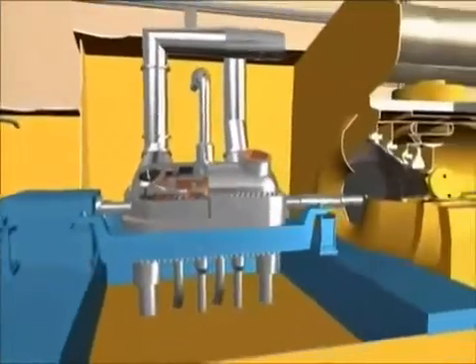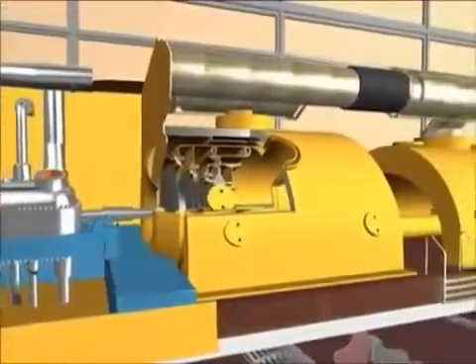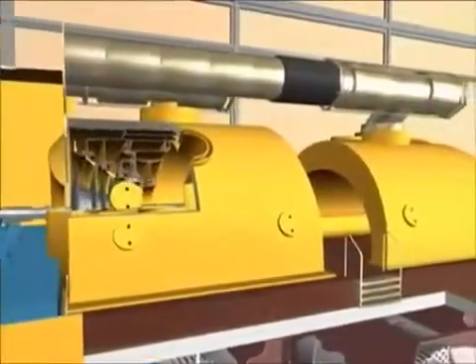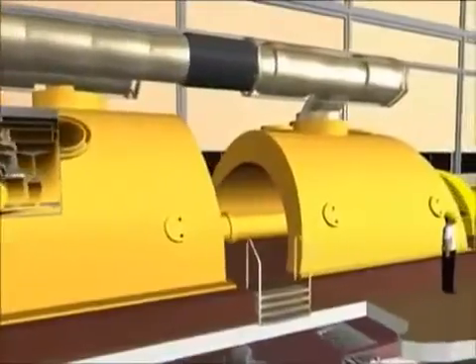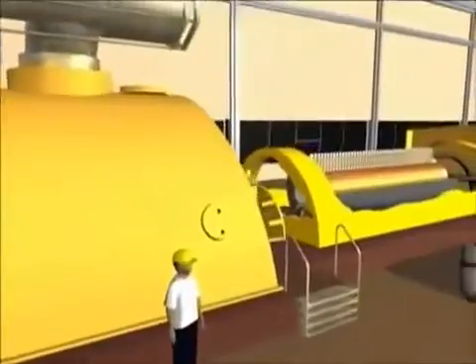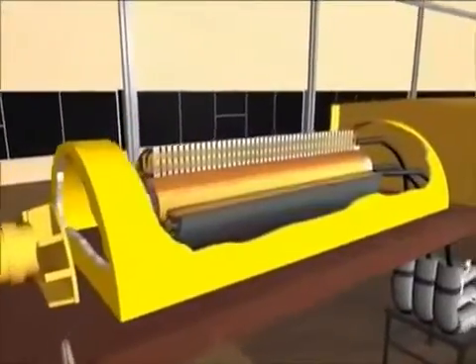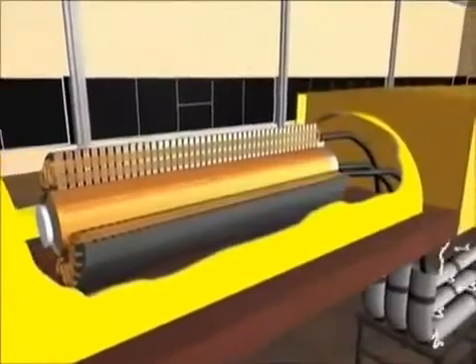Steam goes back to the furnace and arrives at the second turbine. It is 1,000 degrees with 550 pounds of pressure per square inch. The series of turbines spin at 3,600 revolutions per minute. This creates the power needed to spin the turbines and power the generator.